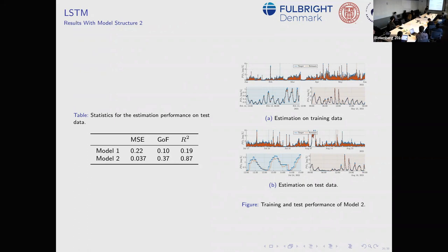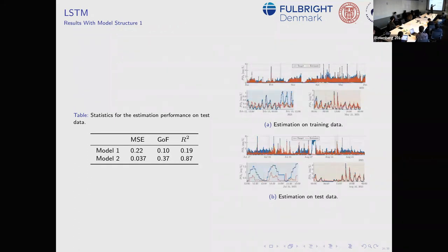One important thing to notice: the non-stationarity very often manifests as the mean changing and the amplitude changing, but very often we still see the period remaining — because dissolved oxygen has a very strong impact and runs in a cyclic fashion. That's essentially the on-off control of the oxygen, which is a very strong driver creating the periodic behavior.